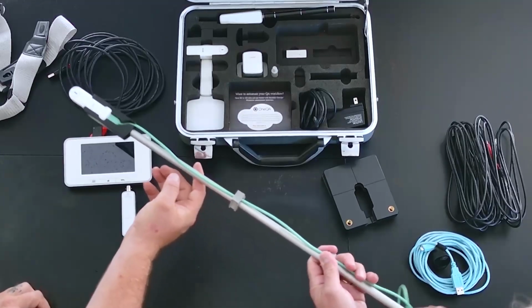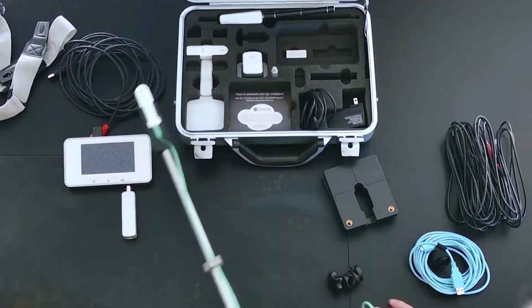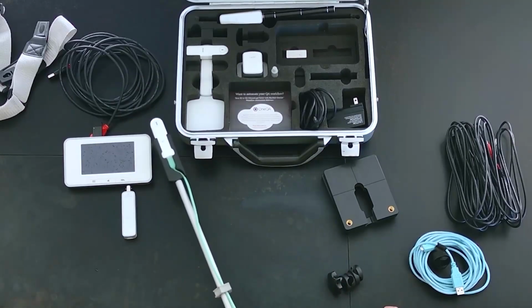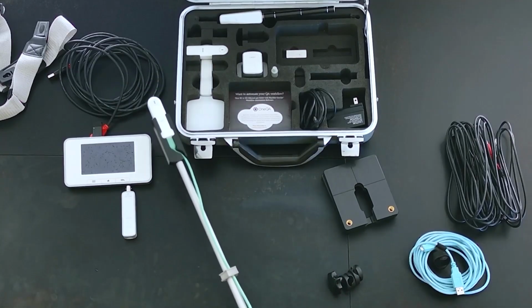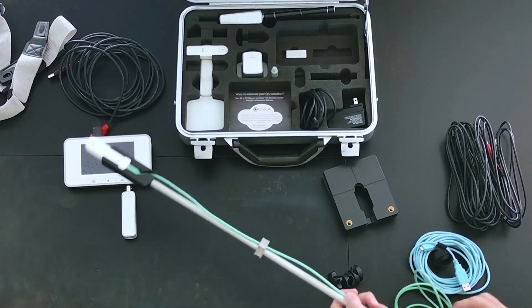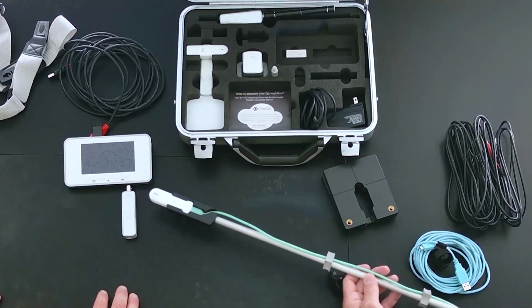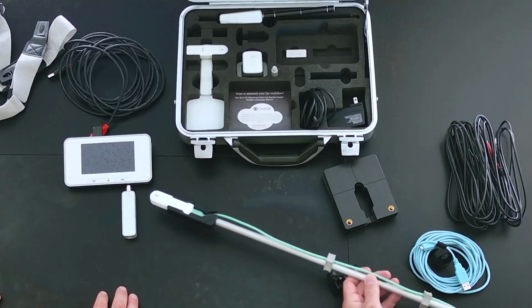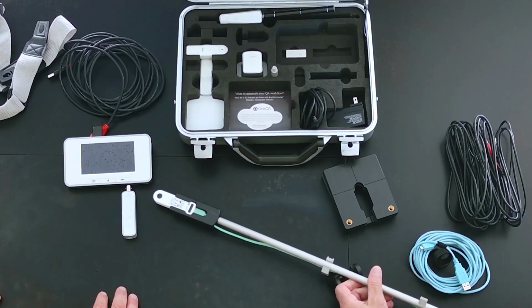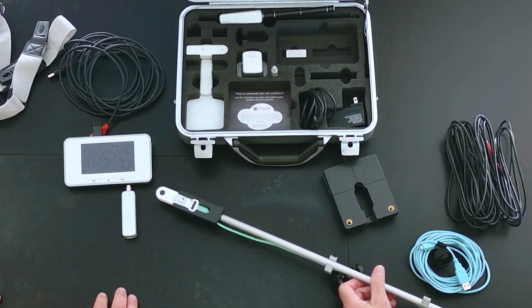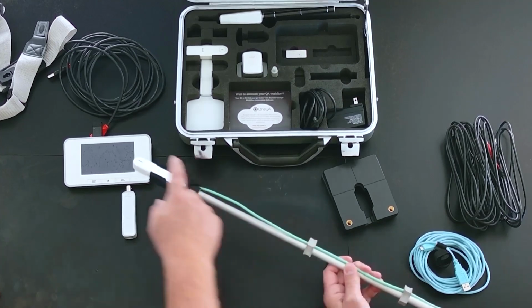So this was originally designed to measure the dose. You put it in the Bucky, measure the dose to the Bucky tray. Justin has another alternative use, which is to measure fluoro low dose. Maybe the tube is pointing up. You just flip it over and put the sensor right on top of the tube, and measure low dose rate fluoro. You can reach right around the side of the Bucky and set this right on the tube.